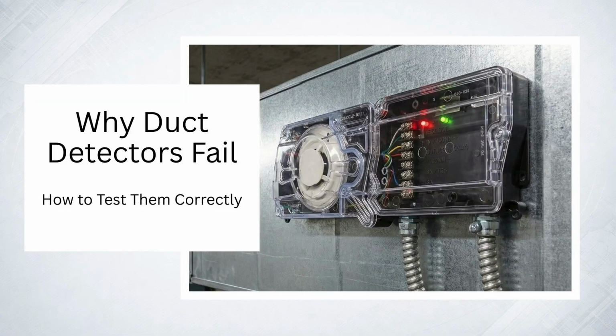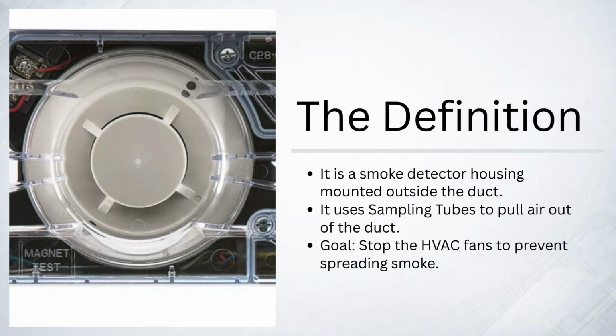If there is one device that causes more arguments between fire alarm technicians and HVAC technicians than anything else, it is the duct smoke detector. These devices are notorious for being hard to find, hard to test, and prone to false alarms. But they are also a critical life safety component. Today, we're going to break down exactly why duct detectors fail, the science of differential pressure that makes them work, and the correct way to test them so you don't get called back at 2 a.m. for a false alarm. First, let's define what we are looking at.